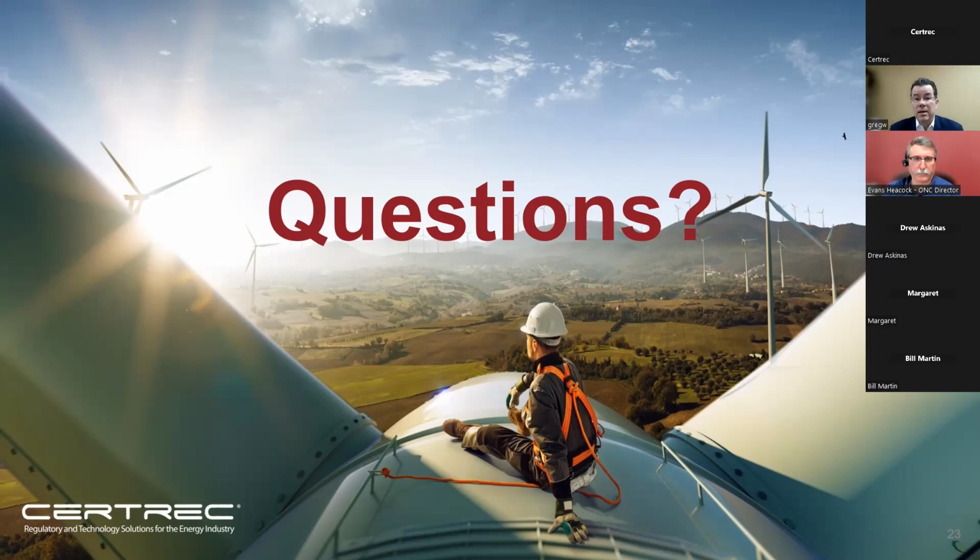Right. The answer is yes. We have many of our customers and installations where vibration sensors are also used. And we're therefore able to correlate what our platform is seeing versus what the vibration scans are showing. In nearly every instance that I can recall, if any issue that's been seen in the vibration profile has been correlated, we also do see it in the electrical signal. And those are even cases where it's on the other side of the gearbox.